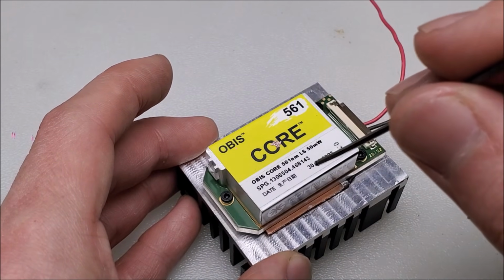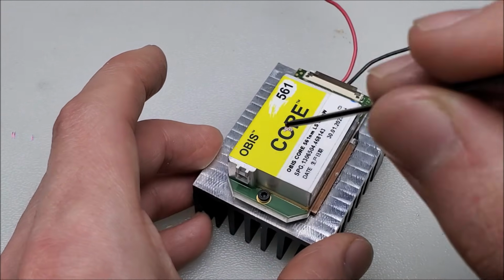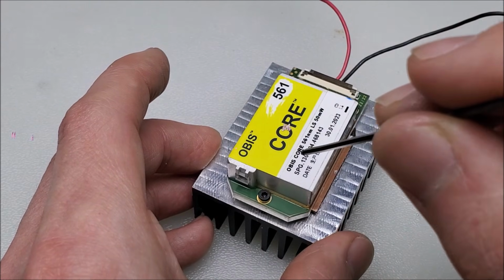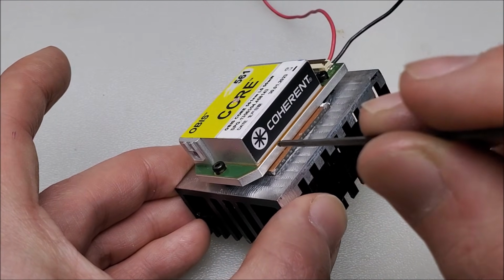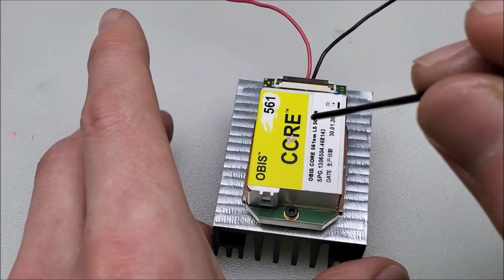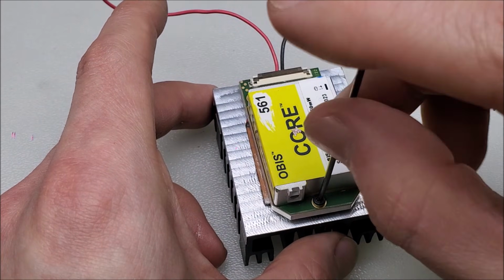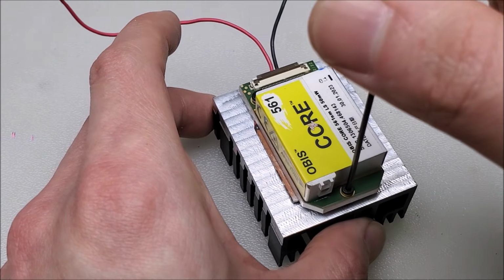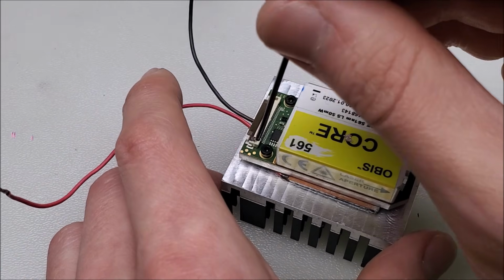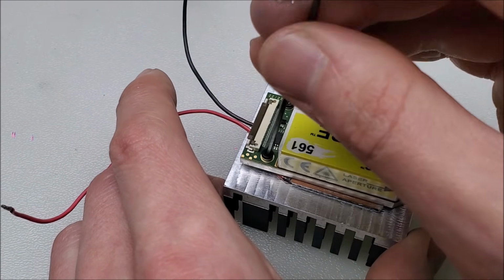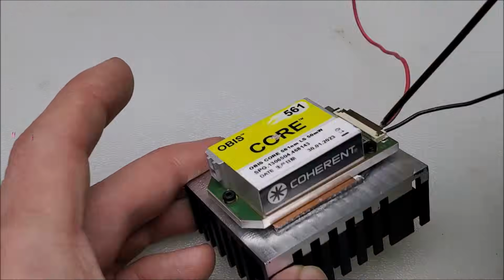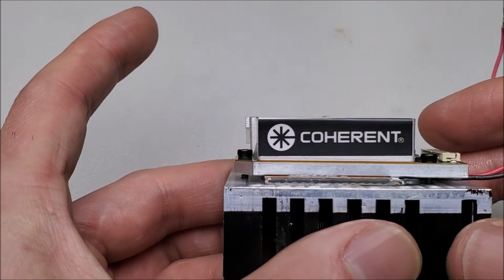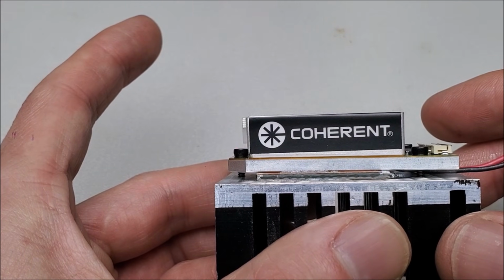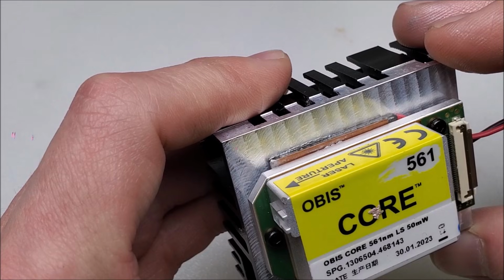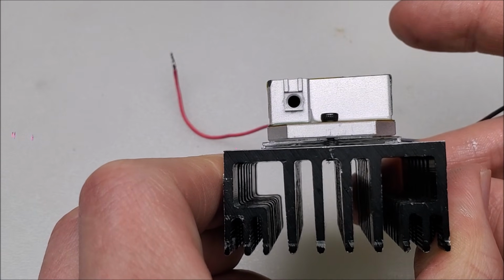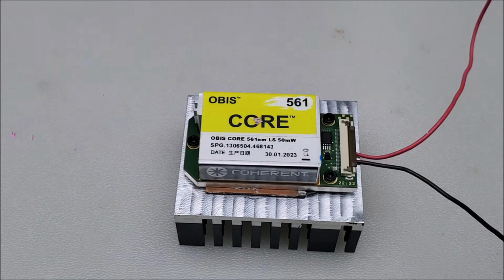And like with most lasers, you want to go around, make sure you don't clamp down the screws too hard, that way you don't ruin the alignment or crack anything that might be connected on the inside of the laser head, or make any clicking, crunching sounds out of the junctions in the thermoelectric cooler. Alright, well, that looks good. Let's start connecting some electronics.